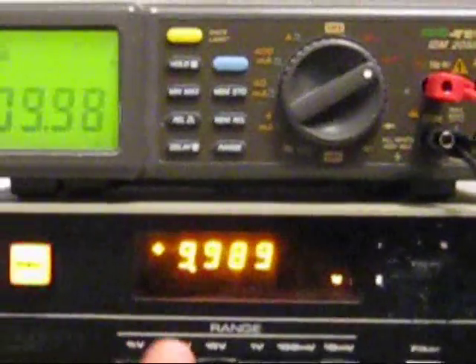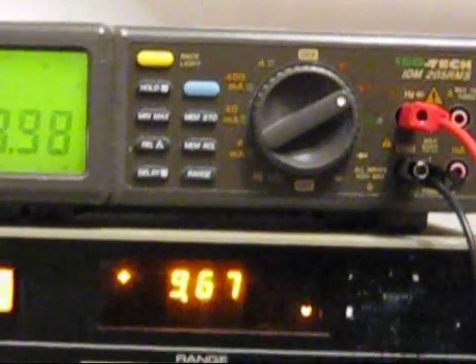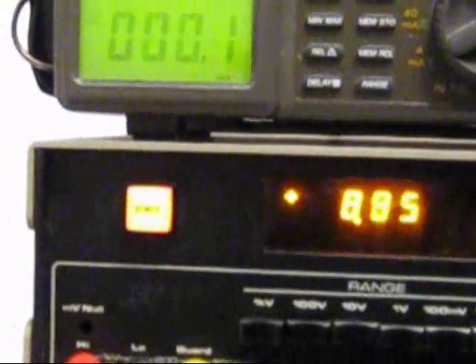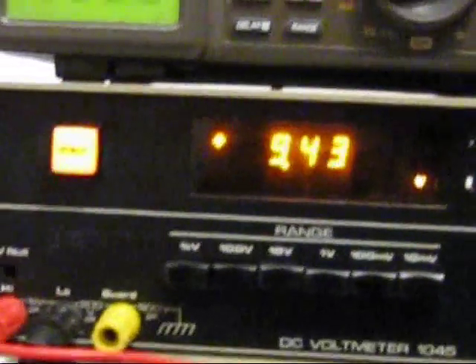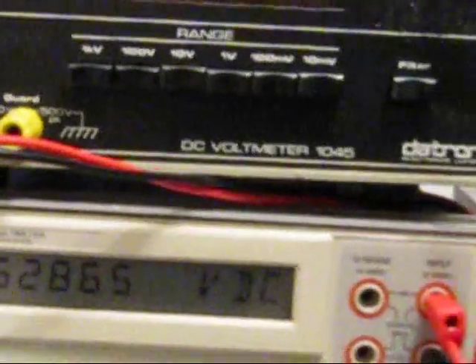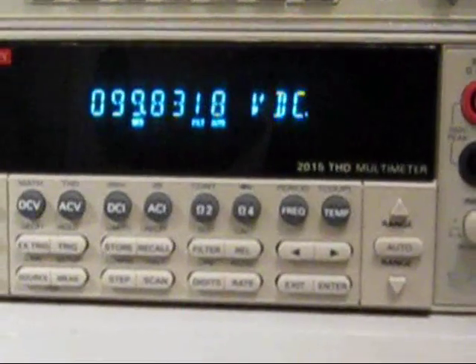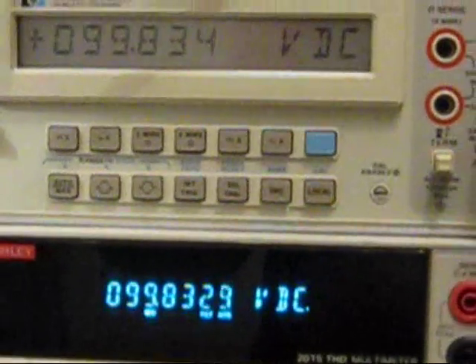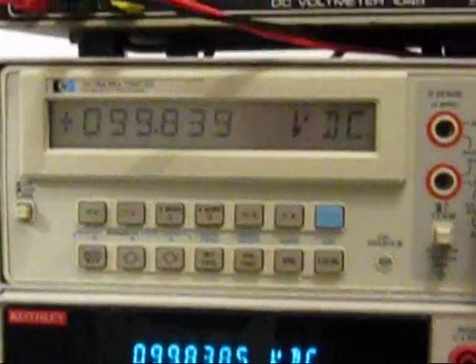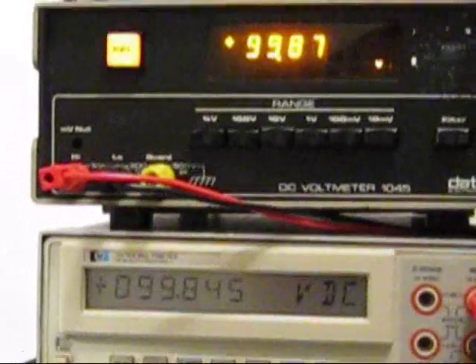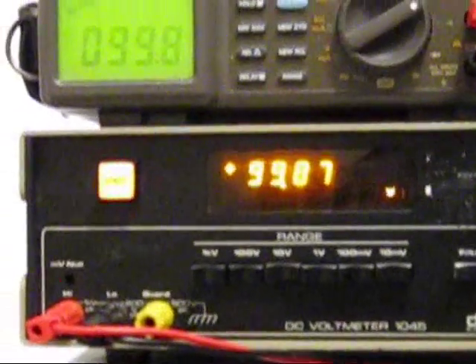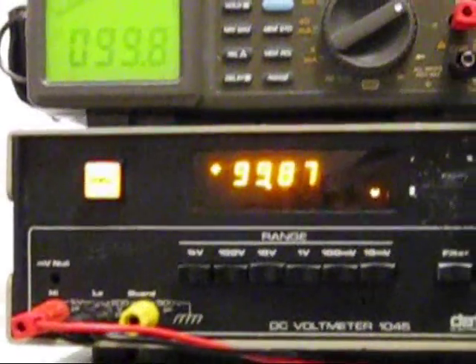So let's remember to manually change the range on the Datron, and reset the calibrator. And now we're up to 99.832 on the Keithley, 99.834 on the HP, and 99.87 on the Datron, and 99.8 on the Isotec.